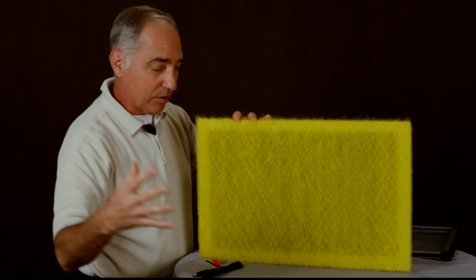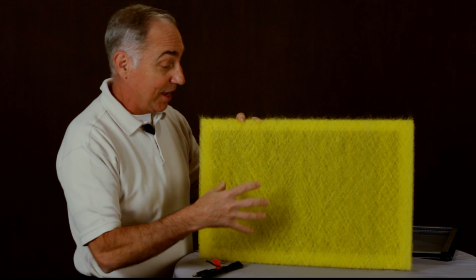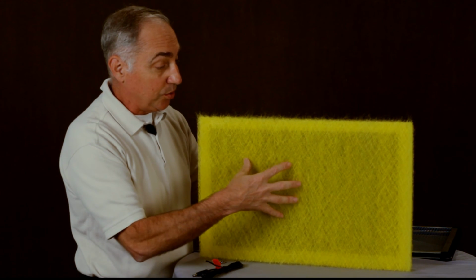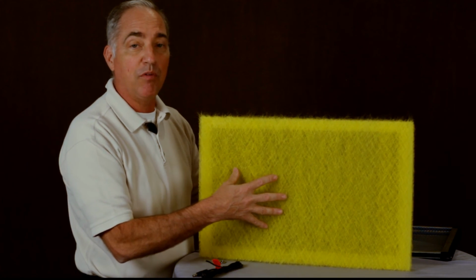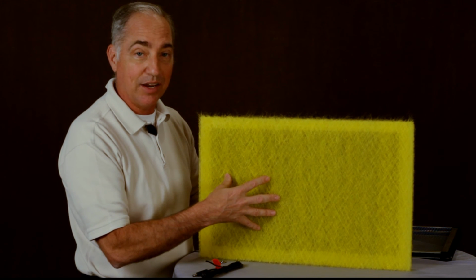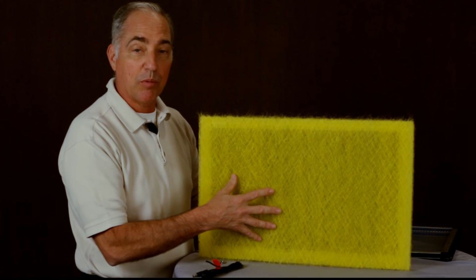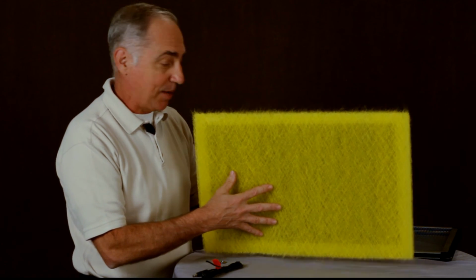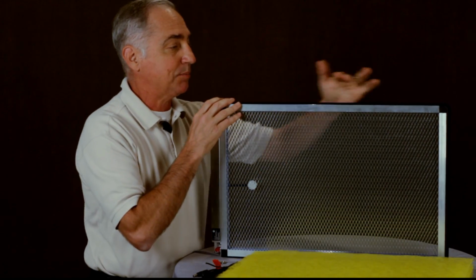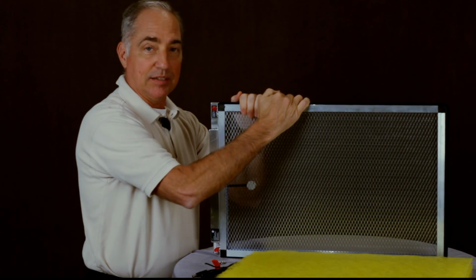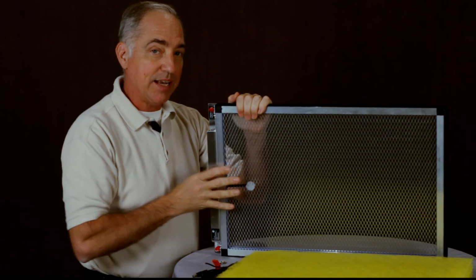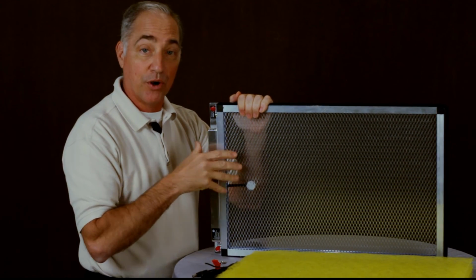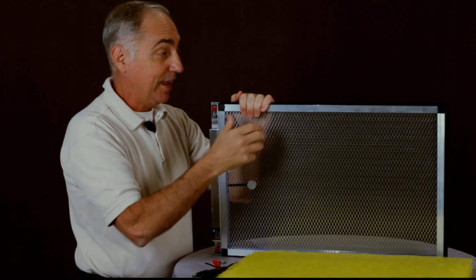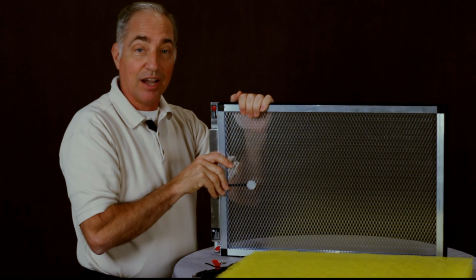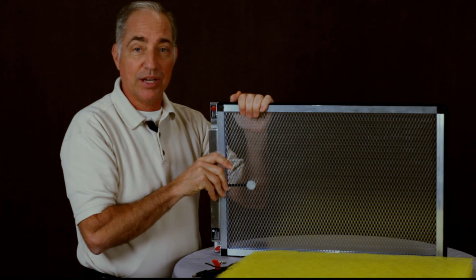So as the particles are coming through here, the positive and negative particles, they get plated or electroplated to the fibers themselves, physically removing them out of the air, not allowing them to go back into the airspace. This gives us, with multiple passes, about 97% at 0.3 microns. I'd also like to point out some new features that we have. If you remember, we used to have clips on top of here to keep this thing tight and closed. But the challenge with that is sometimes the clips would get caught on a burr or something inside the filter rack, and they would open up while you're pulling it out and they get stuck. So you'd almost have to damage the clips in order to get this out.